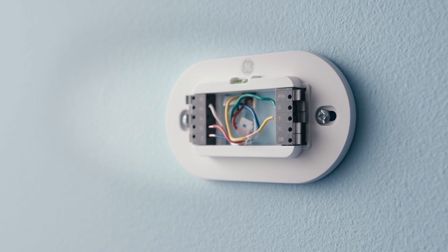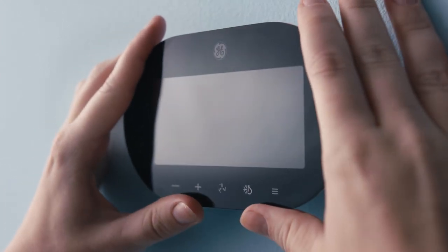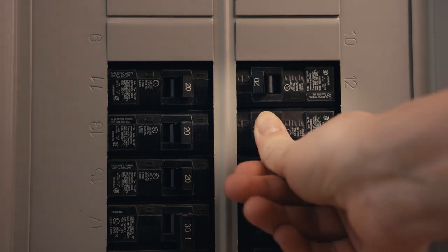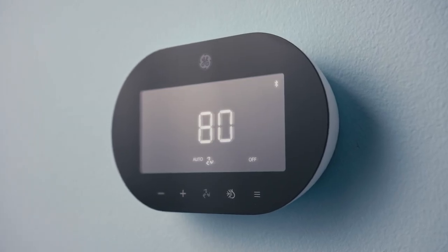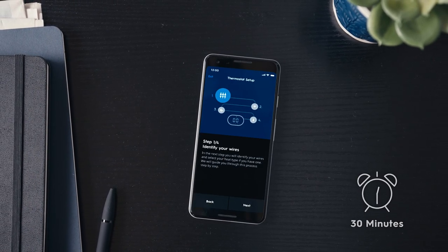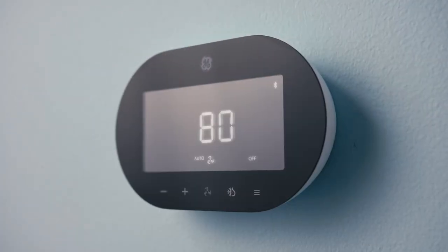Step 5: Mount your new smart thermostat onto the backplate. The thermostat control buttons should be along the bottom. Once aligned with the backplate, gently push the thermostat on either side of the screen until it clicks into place. Step 6: Restore power to your HVAC system to ensure everything is working correctly. If things are running smoothly, your thermostat should turn on automatically. Within 30 minutes of installation, begin setup in the Cync app. After 30 minutes have passed, you can re-enable setup mode by gently removing the thermostat from the backplate and reattaching it.